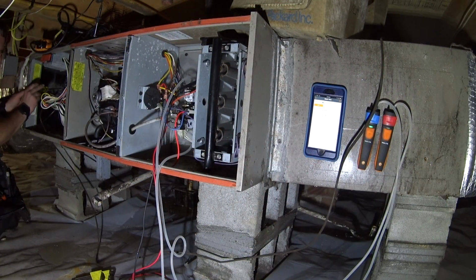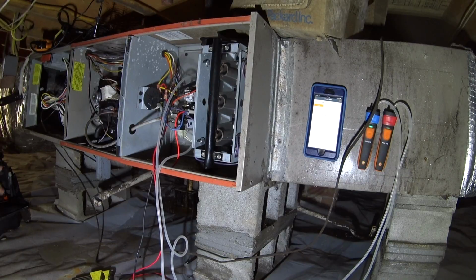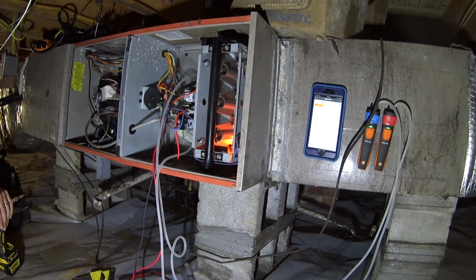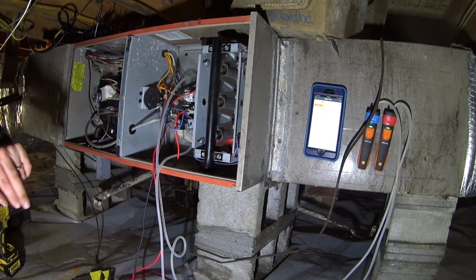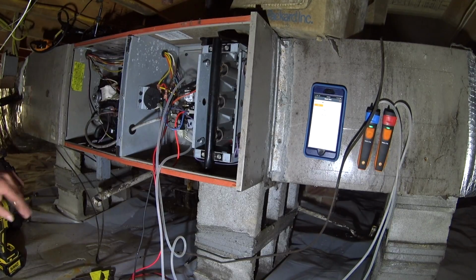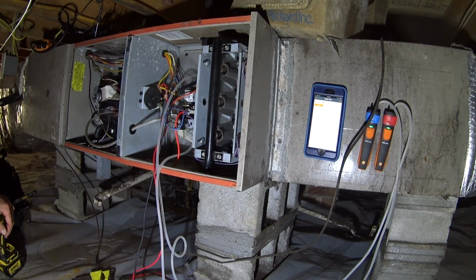David Cameron, while I was at his training class, suggested that you never jump a thermostat out with the red wire connected. So we're gonna hit the white W1 and the red wire, and we're gonna put the blower door on. Gas pressure in first stage is 1.6, and we're not going to hit second stage, but we're going to take combustion readings before we jump up to second stage.